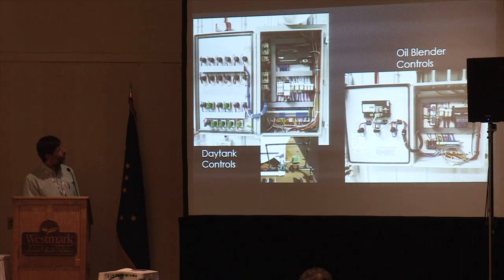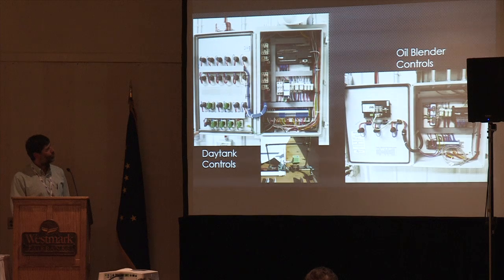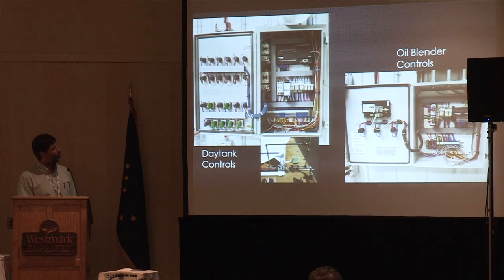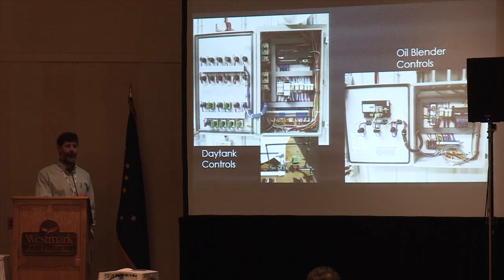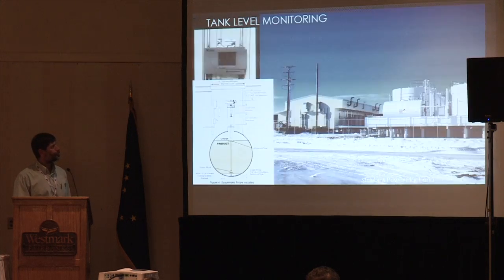To prevent any sort of accidental spill, we also have a motor-operated, or solenoid, valve out in the tank farm, so that when the plant operator pushes the button to fill the day tank, it opens an electronic valve out in the tank farm that isn't open all the time. That way, if there was a break in the line, you don't get spills.